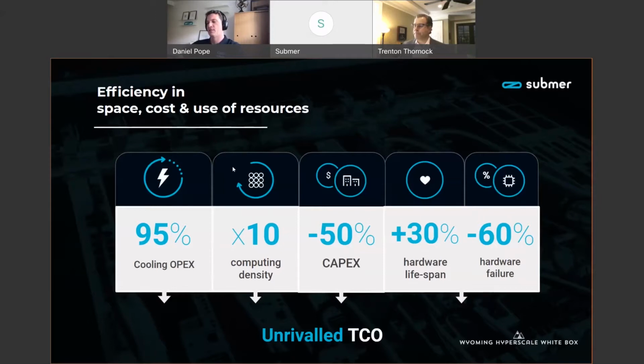Something that's hard to wrap your head around when we refer to the PUEs we can typically achieve with immersion is that a big percentage of the savings actually comes from the removal of fans, especially in higher density hyperscale hardware, which usually runs in very warm data hall temperatures to try to gain efficiencies in the system.